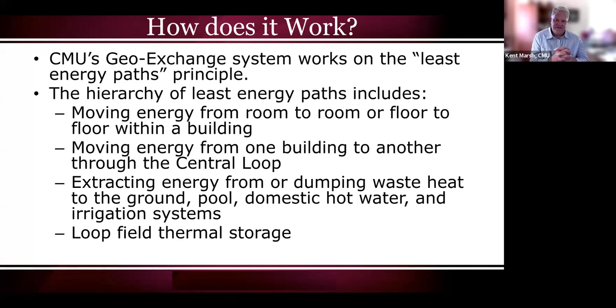Let's assume it's the middle or end of summer, and even though we're dumping as much waste heat as we can, there's still excess waste heat in our central loop. That waste heat contained within the water is sent down into the ground in one of those 8 or 9 drill fields. As that warm water moves through the drill field, the earth extracts heat from it, so when the water comes back to the surface, if we've designed the system correctly with as many cooling loads as heating loads, it returns at the deep earth temperature. Then it goes back to a building and the whole process starts again.